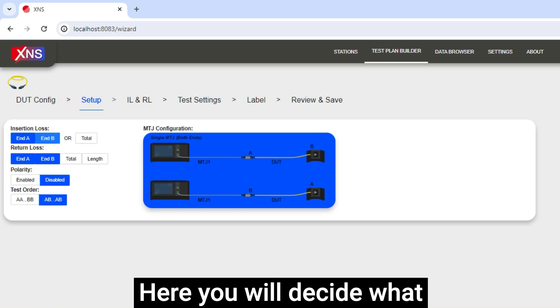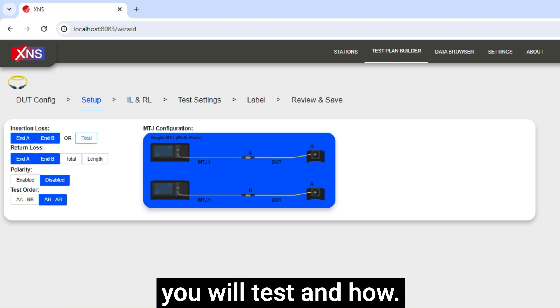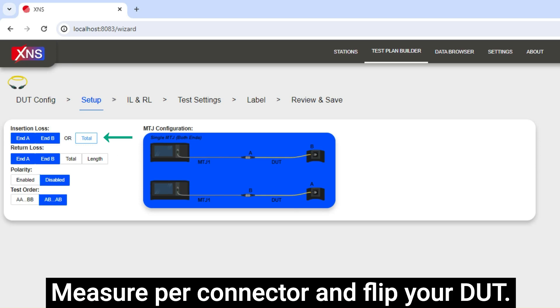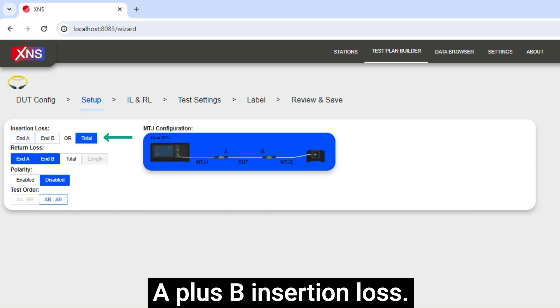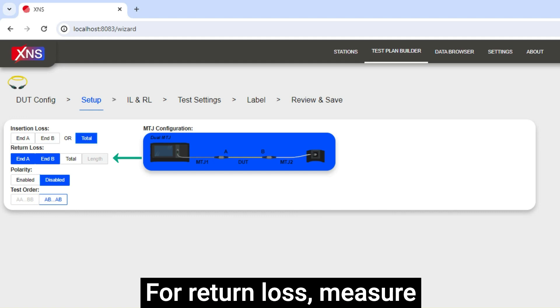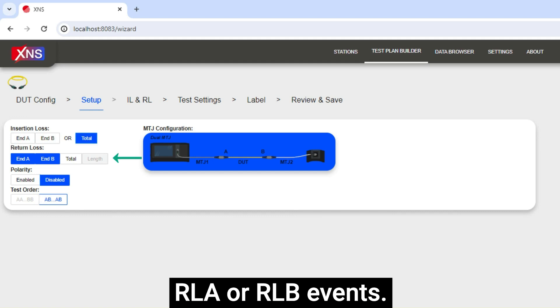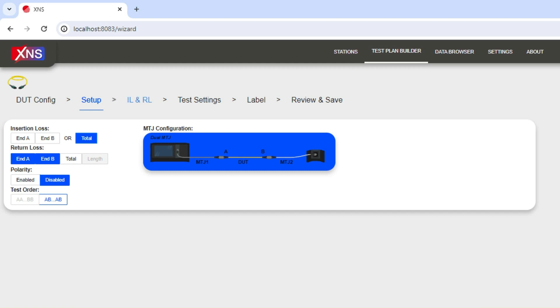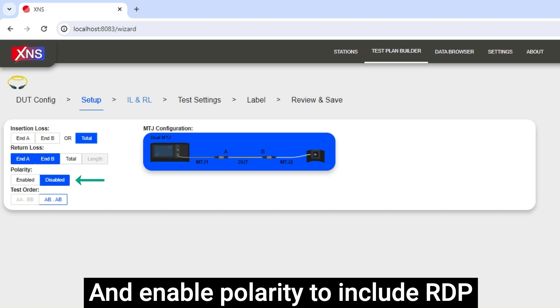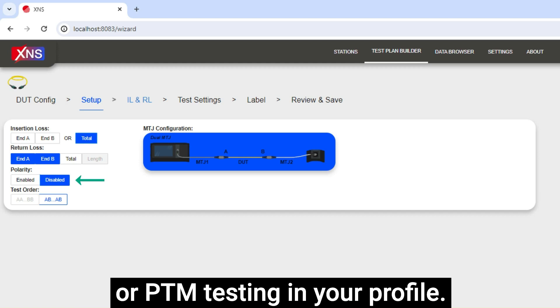Here you will decide what you will test and how. Measure per connector and flip your DUT, or measure total and measure A plus B insertion loss. For return loss, measure RLA or RLB events, or RL total for the total RL window. And enable polarity to include RDP or PTM testing in your profile.